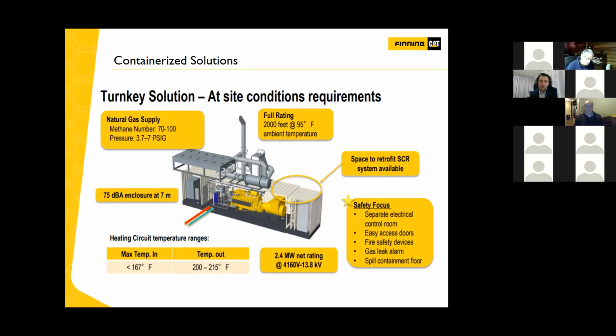Altitude and ambient temperature are items we have to figure out, since we might see some derates based on that. Sound requirements at site are also important—it's best to be aware of site space, as some city noise bylaws are impossible to meet if the product is installed close to the property line. I say impossible because I've seen the guidelines for the City of Edmonton and City of Calgary, and if you're at the property line, you can't meet those requirements. But if you're doing a wastewater station or a rec center, there's usually a lot of field and yard around those installations.